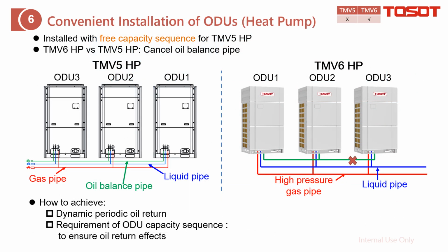Convenient installation of outdoor units. On this slide, I compare the GMV5 heat pump and GMV6 heat pump installation. Let's focus on the GMV5 heat pump. On site, you need to install the gas pipe, liquid pipe, and also the oil balance pipe, right? But for the GMV6 heat pump, as we cancel the oil balance pipe, you just need to install the liquid pipe and gas pipe, but this time it is a high pressure gas pipe because we integrate heat pump and heat recovery together. And this is what we can get. So we need to sacrifice something, right?